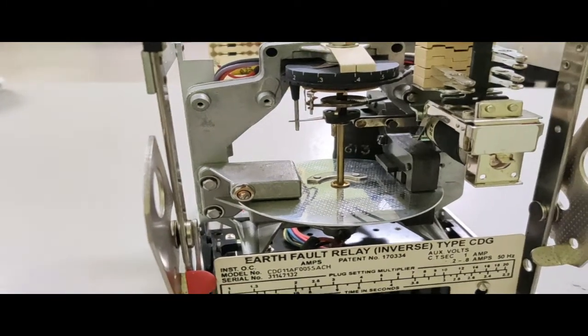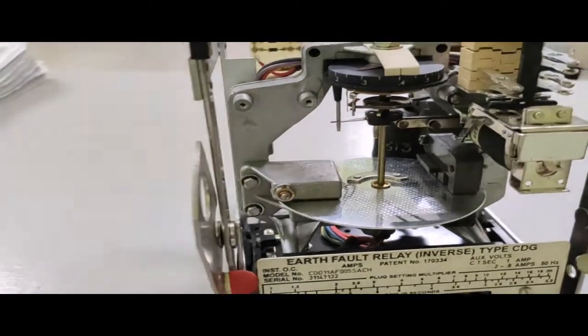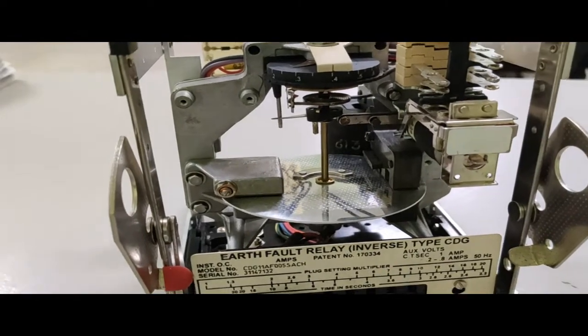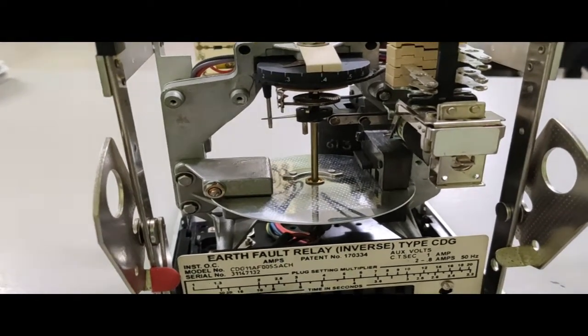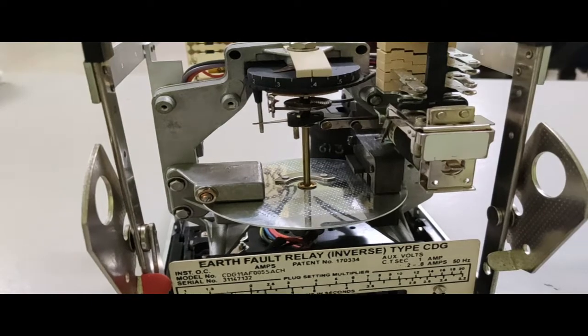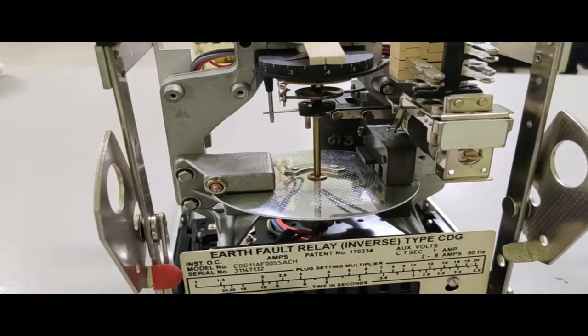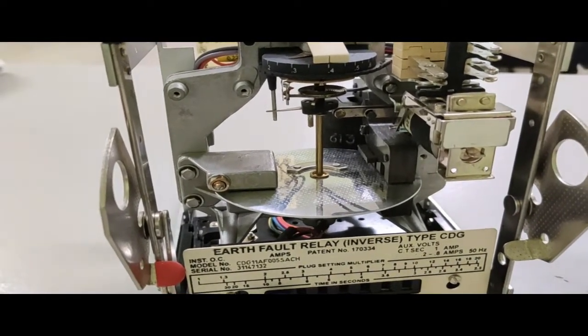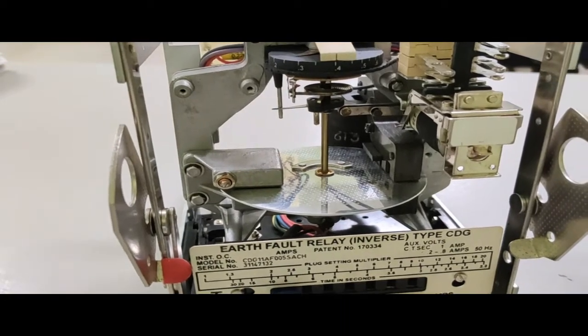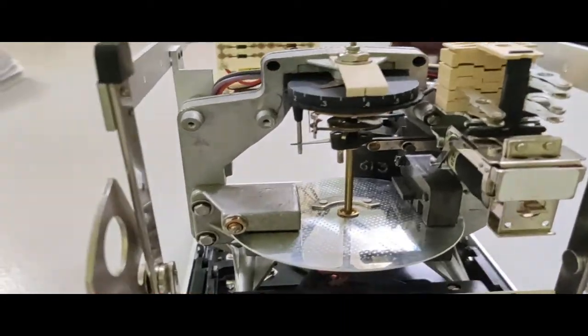So why is this time required? Because so many faults in the power system are transient in nature. That means it seems like a fault, but after some time, after some cycles rather, the fault automatically dies down. So no relay operation is required, and within this time nothing has happened, nothing is hampered, and no overcurrent has flowed to the circuit.